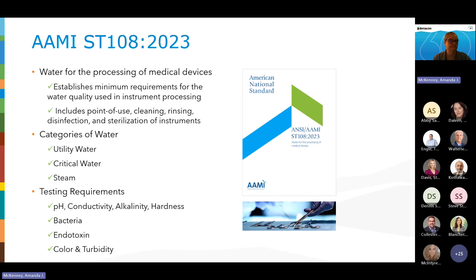Water testing requirements are defined by the type of water and how it's used. You see here on the slide, the categories of water are broken down by utility water, critical water, and steam. I won't go into a lot of detail on what those mean, just understand that there are different testing requirements for those different categories of water, and that it's important that you sample the different constituents for each of those categories of water. It requires an initial performance qualification followed by monthly or quarterly testing for various constituents. This will include water generation systems and the point of use.